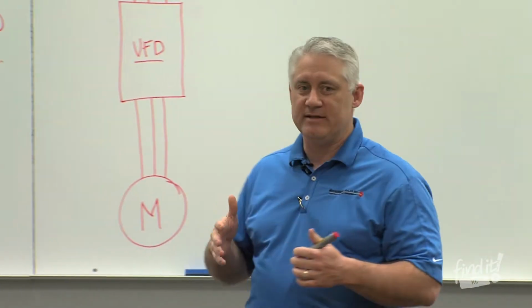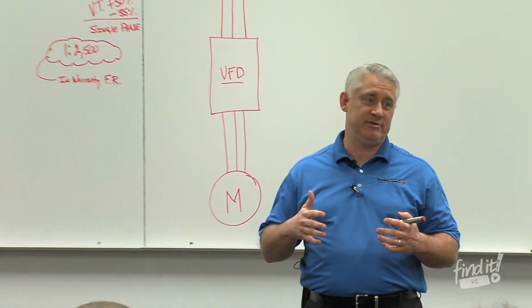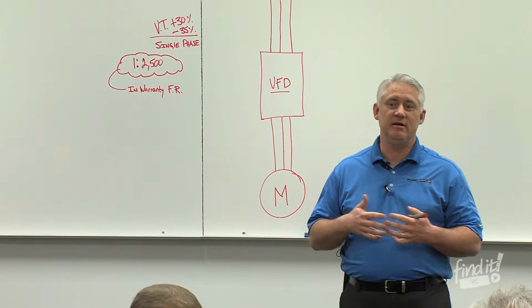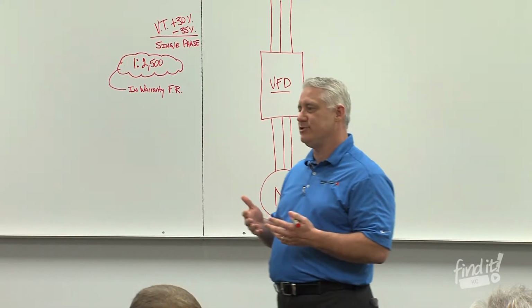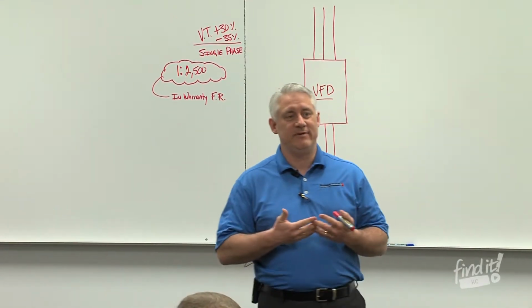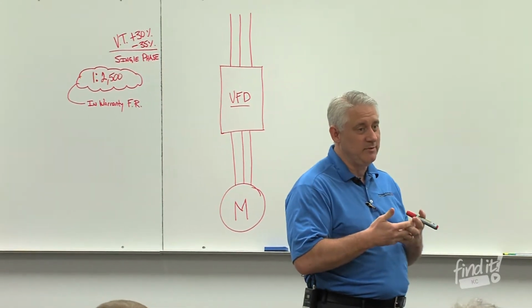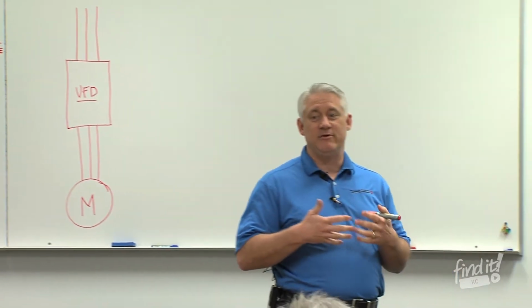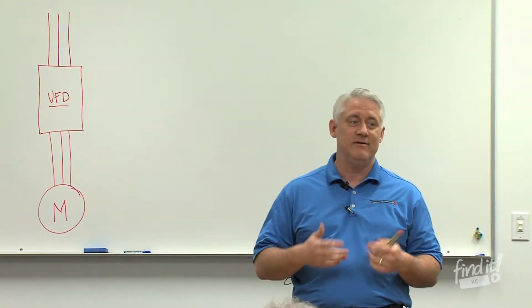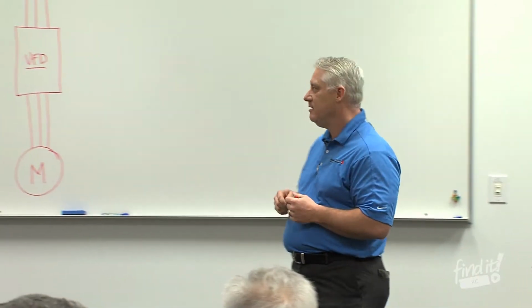So everybody understands, Richard talked a lot about the drive. Back in the 80s, failure rates on drives were very, very high. Drives were new technology. The componentry wasn't mature enough yet. So we had a very high failure rate. So much so that in my early days, when I would go to install a VFD or service a drive, I would bring a spare with me. The failure rates were that high.